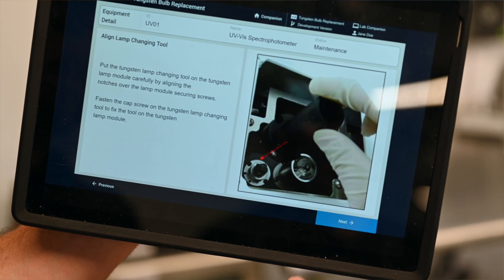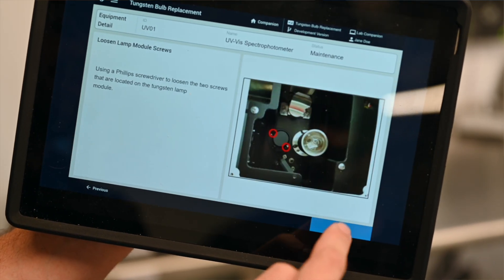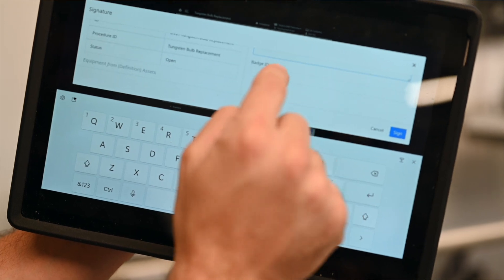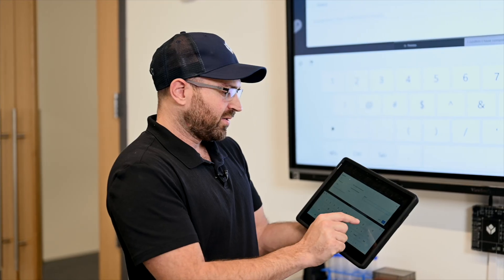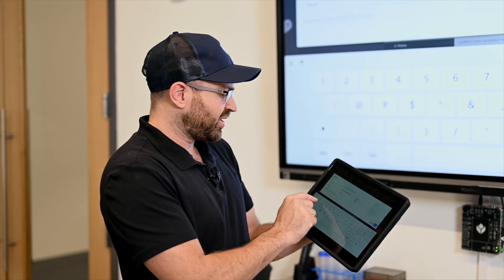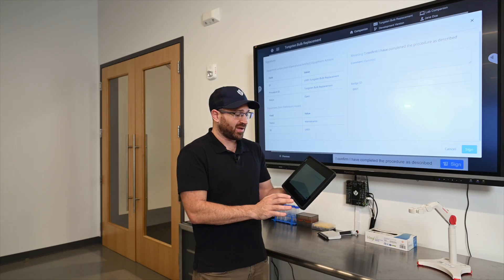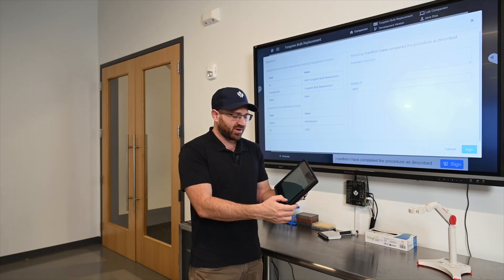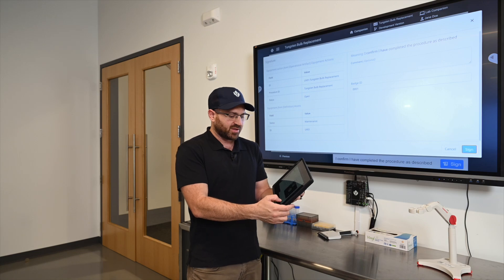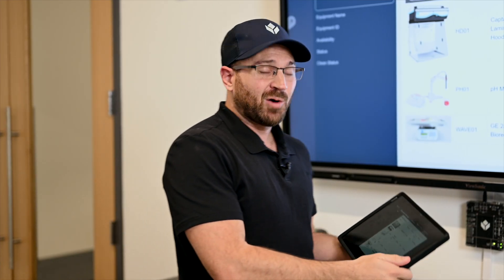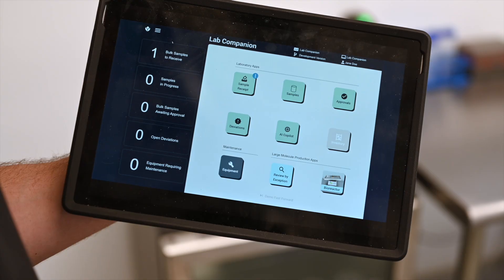I can sign off on these, follow the instructions, and sign off that I've completed this procedure. Completing this procedure will put this equipment into a non-calibrated state, which means that if I were performing the pH test and I went to run that, I would not be able to do that until I perform the calibration procedure.